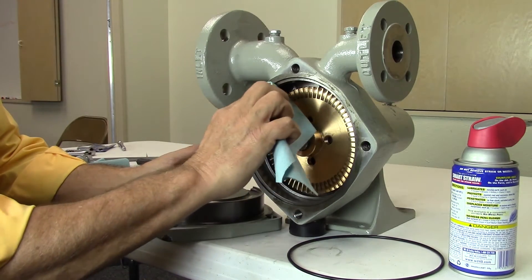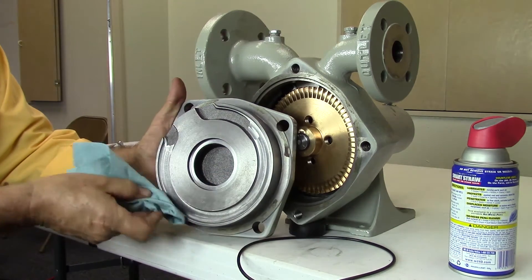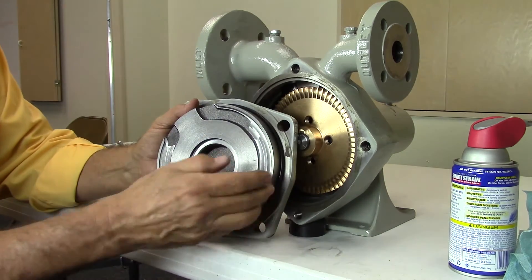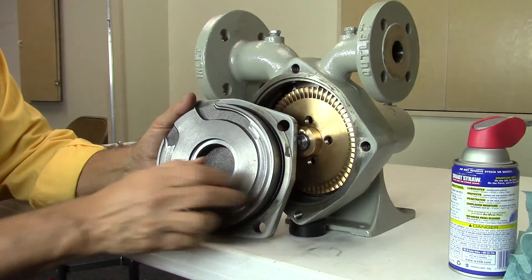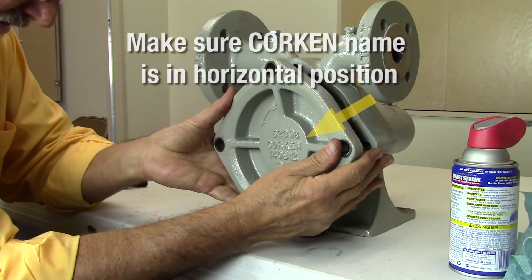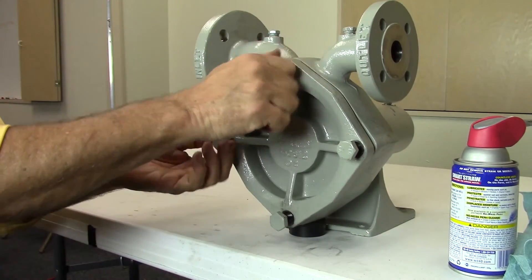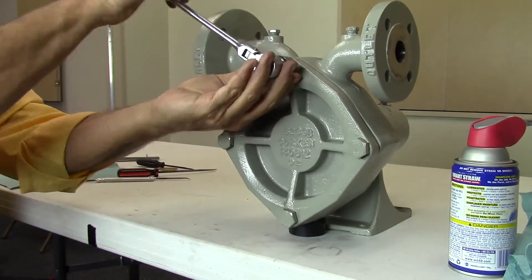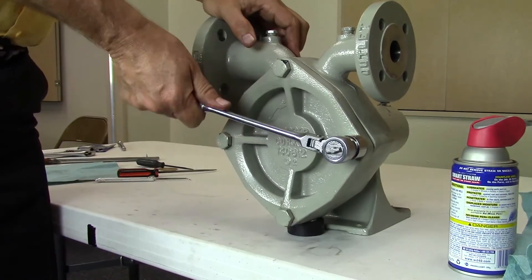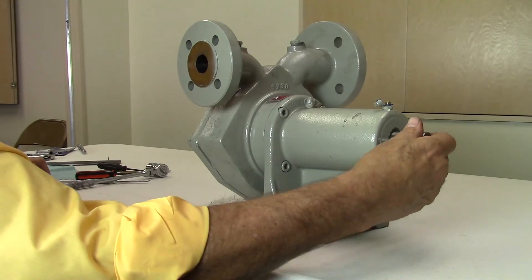Before installing the cover head, gently file or use emery cloth on the mating surfaces to make sure they are clean and smooth. Lubricate the new O-ring and install in position as shown on the cover head. Install the clearance shims at this time if you are working on an older model. Align and install the cover head onto the pump case making sure the Corken name is in the horizontal position. Install the cover head bolts and tighten in a criss-cross manner with a socket or an adjustable wrench. Torque the bolts to specification listed for your model in the installation, operation, and maintenance manual. Make sure the pump shaft turns freely.